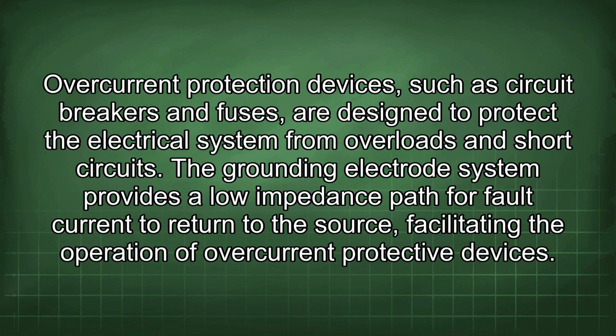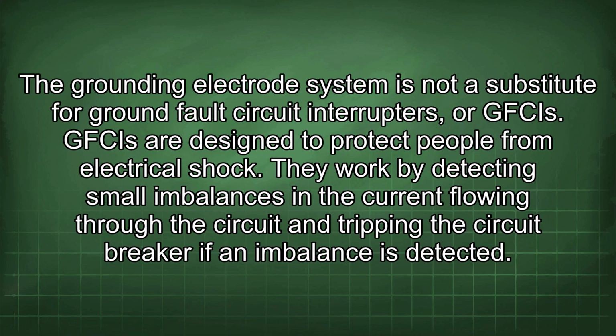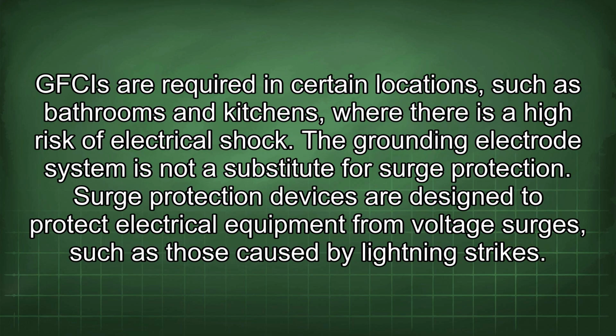Overcurrent protection devices such as circuit breakers and fuses are designed to protect the electrical system from overloads and short circuits. The grounding electrode system provides a low impedance path for fault current to return to the source, facilitating the operation of overcurrent protective devices. The grounding electrode system is not a substitute for ground fault circuit interrupters, or GFCIs. GFCIs are designed to protect people from electrical shock. They work by detecting small imbalances in the current flowing through the circuit and tripping the circuit breaker if an imbalance is detected. GFCIs are required in certain locations, such as bathrooms and kitchens, where there is a high risk of electrical shock.